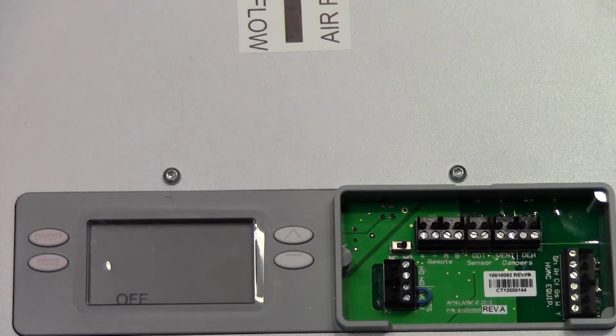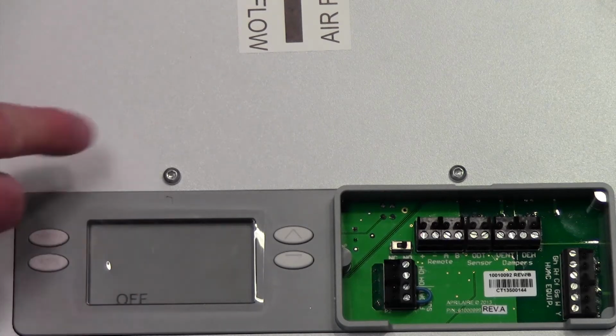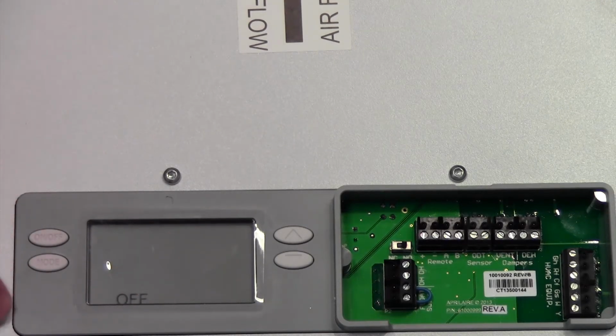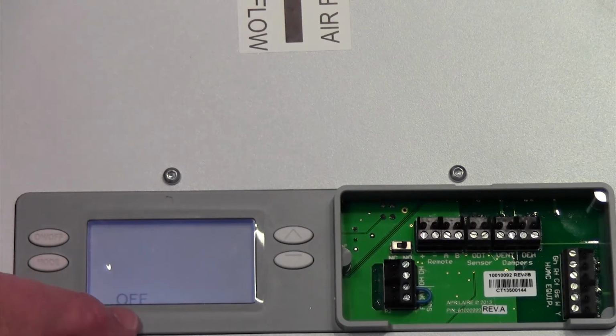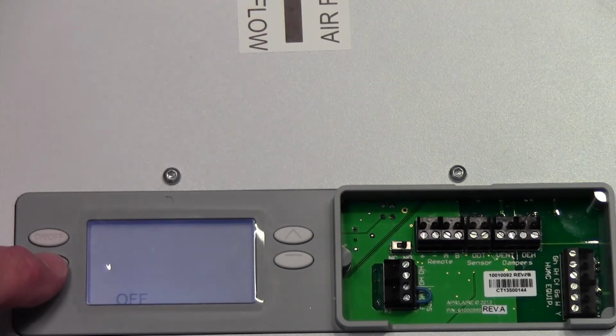But if we're going to enable some of our features that we have or use external control, we'll need to get into the setup menu. To enter the setup menu, the first thing that we want to do is any button push of this turns on the light. And from the off position, we have to be in the off position. If we hold the mode button down for 3 seconds, we will go into the installer setup menu.